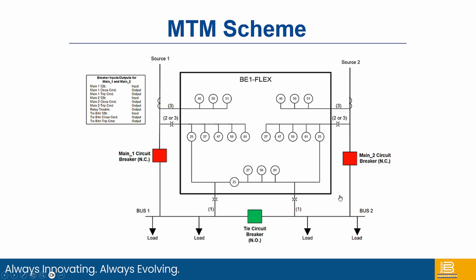Anytime you're doing a control of closing breakers, you almost always want to do a sync check function to make sure that those voltages and angles are within tolerance, and that's assuming that you have other load sources or any other non-zero power condition down towards the load side. In addition to that, again, I mentioned the intertie stuff. We can do all those intertie functions at those points if you wish, in addition to all the other stuff.